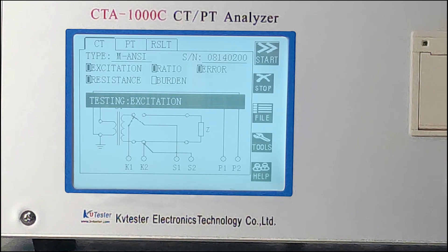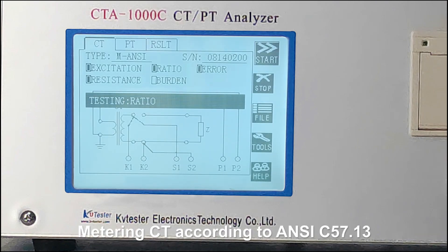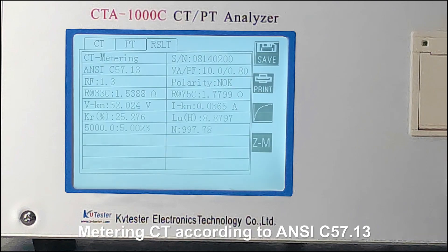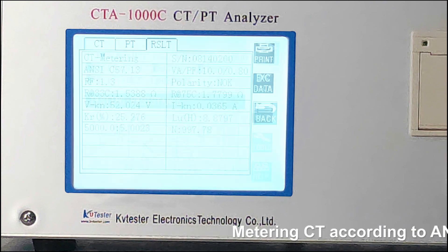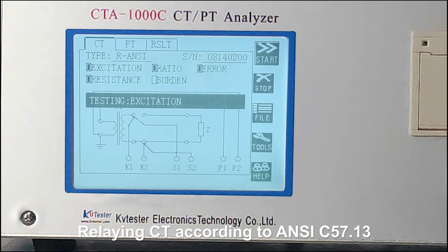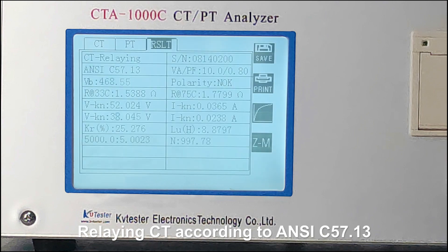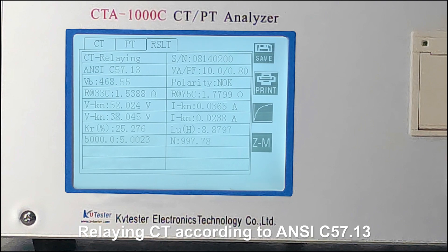This result is coming from a Metering CT, according to ANSI C57.13. The analyzer calculates both 45-degree and 30-degree knee points simultaneously. Ratio error and phase angle are also measured.